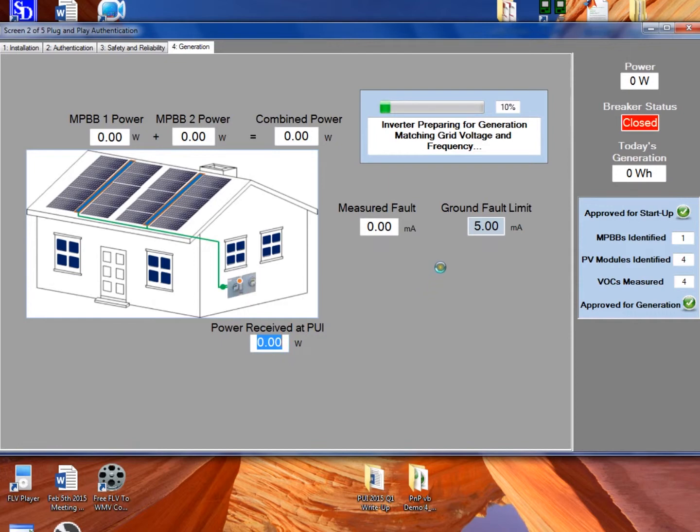Now the system is approved to generate. The PUI sends a signal out to all inverters saying they can generate, and they have to wait the required five-minute period where they verify stable grid voltage and grid frequency within certain bounds. This waiting period has been sped up for this demonstration video. After waiting five minutes, the system is now generating. We can see that we've got only one inverter generating — as we only found one inverter.